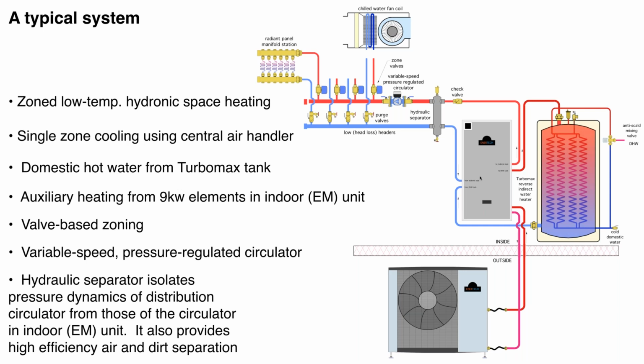That's important because actually that circulator that's in the indoor unit of the heat pump is a variable speed circulator, and it's being controlled based on the logic of the heat pump. So we don't want another circulator in the system to interfere with the speed that that circulator wants to run at, and vice versa. This circulator is common today. In fact, we talked about it last week. Pretty much all the circulator manufacturers now offer what is called a variable speed pressure regulated circulator. This is a circulator that will automatically adjust its speed as it senses opening and closing of, in this case, zone valves.